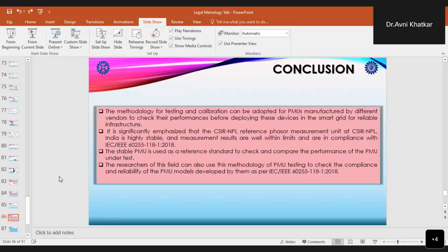So I would like to conclude by saying that the methodology for testing and calibration can be adopted by the PMU manufacturers by calibrating the PMUs from the different vendors in order to check their performance before deploying these devices in the smart grid for reliable infrastructure. It is also significantly emphasized that the CSIR NPL reference phasor measurement unit is highly stable, and all the measurement results are well within the limits and in compliance with the latest IEEE standard. This stable PMU is used as a reference standard in order to check and compare the performance of the PMUs under test.